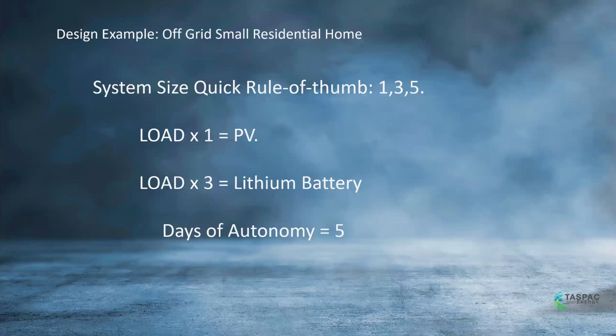And some customers that I've got have actually stuck to this rule and are using the amount of load that we estimated, usually plus or minus 20%. But some customers I've got, the only time their generator runs is once a month on a test run. They've gone through, even the storms that we had recently, and never needed the generator. The only reason they started it was just to make sure it was running.